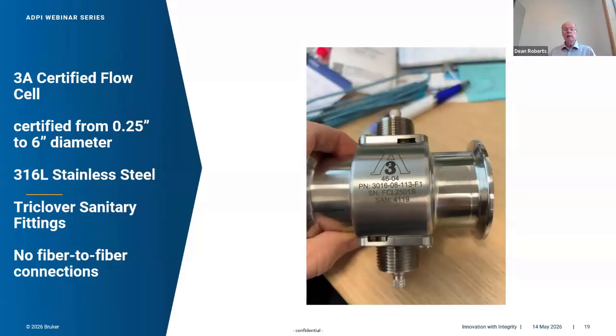Next slide, please. So this is the 3A flow cell that Custom Sensors and Technology came up with. And it's certified by 3A for diameters from 1/4 inch, which would be just very small lines and maybe a pilot type facility, all the way up to 6 inches in diameter. It's currently made from 316L, but we're also looking at making a cell out of Hastelloy C276, because in some of the European factories, they're required to use hypochlorite as their CIP solution for raw milk. And 316L will not stand up to hypochlorite as a cleaning solution. We've got Tri-Clover sanitary flange fittings, and there are no fiber-to-fiber connections inside the flow cell.